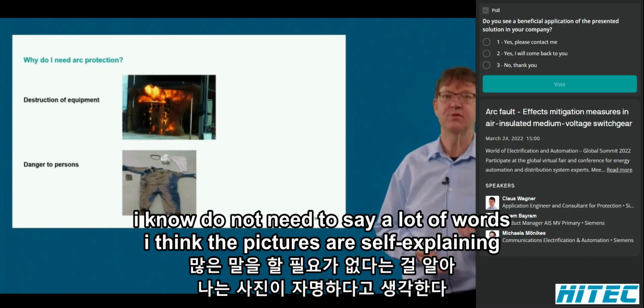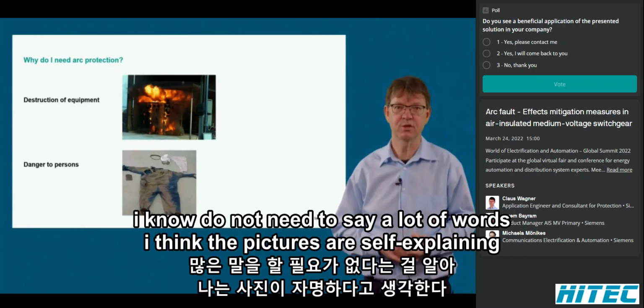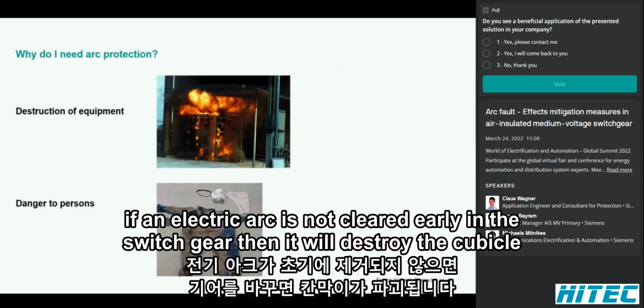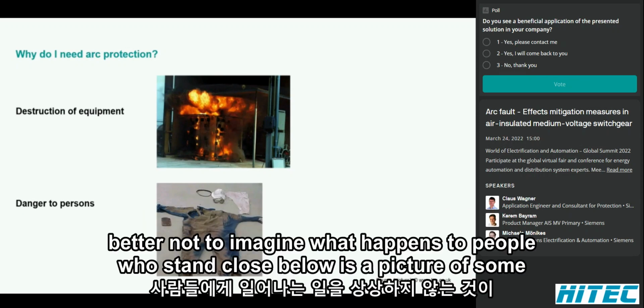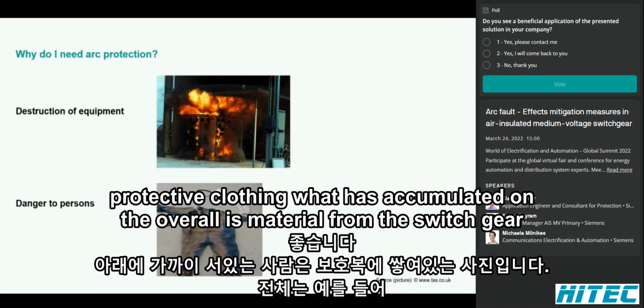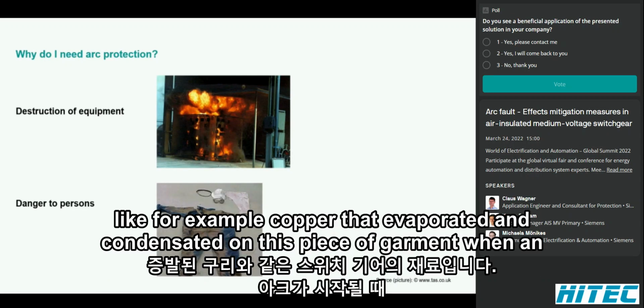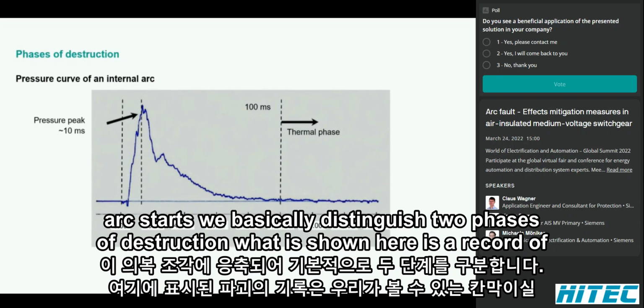I do not need to say a lot of words. I think the pictures are self-explaining. If an electric arc is not cleared early in a switchgear, then it will destroy the cubicle. Better not to imagine what happens to people who stand close. Below is a picture of some protective clothing. What has accumulated on the overall is material from the switchgear, like for example copper, that evaporated and condensated on this piece of garment. When an arc starts, we basically distinguish two phases of destruction.